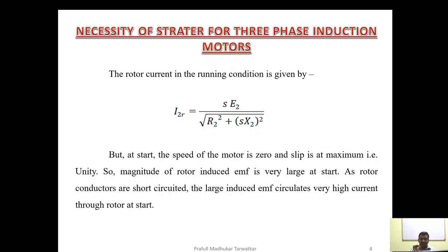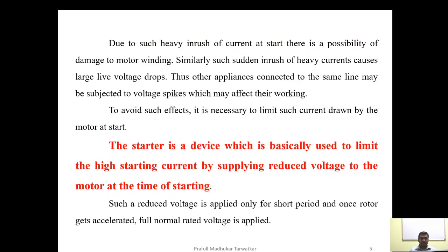So it is very important to control the value of current I2 during start, and hence a device called a starter is used. As per the technical definition, a starter is a device basically used to limit high starting current by supplying reduced voltage to the motor at the time of starting.